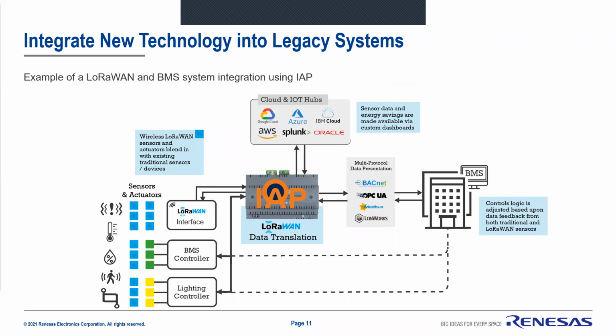So with IAP, we've enabled it to digest the local LoRaWAN data without having to go to that wide area network. We can ingest it directly on an edge device, and push that data out directly on premise to an existing BMS, whether that's BACnet, OPC, LonWorks, or Modbus. So the local BMS now has a whole slew of new sensor data available to it that can be leveraged to achieve some sort of outcome.